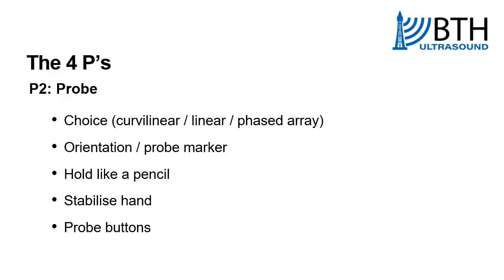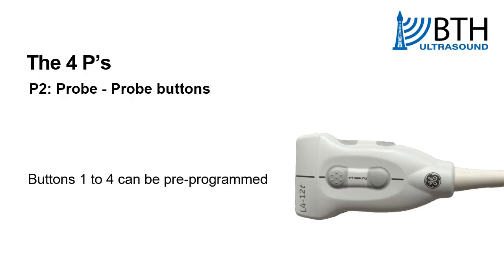Next, some of the probes have buttons on them, and if you program these buttons in a certain way, they can help you stop needing to move the probe or move yourself or to reach across to the machine. So at the moment we have a machine that has them on the linear probe, and I have set them for presets to enable you to freeze the image, and one of the more important things, to store an image. So you can press one of the buttons that has been preset to that, and you can actually take a video clip without having to reach across to the machine. Again, this just allows you a little bit more comfort, a little quicker, and it means you don't have to twist and turn to reach the machine if it's just slightly out of reach or across the bed from you.